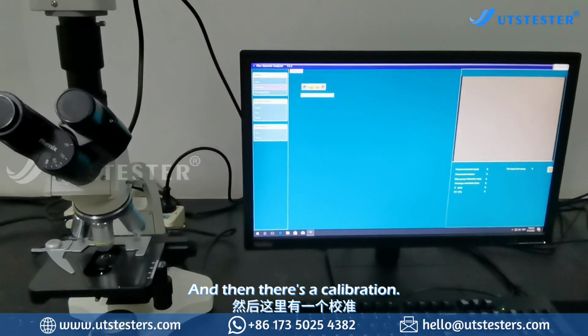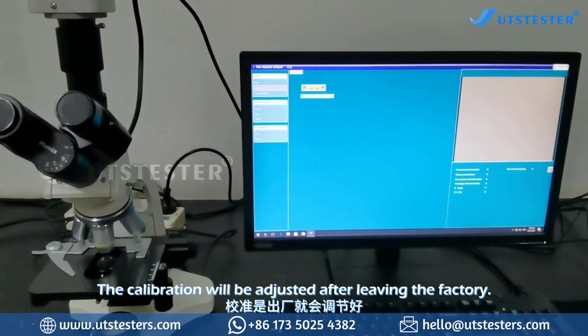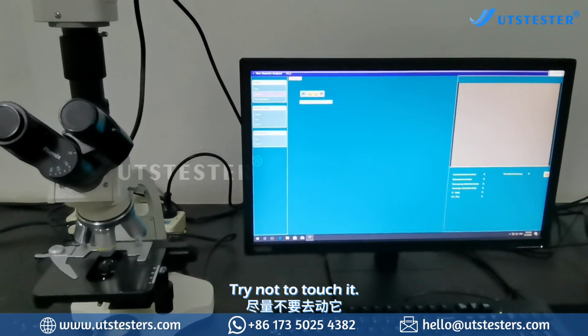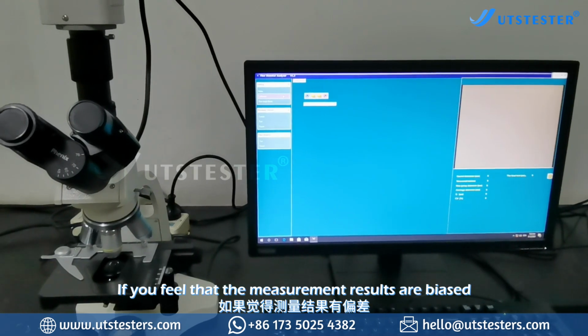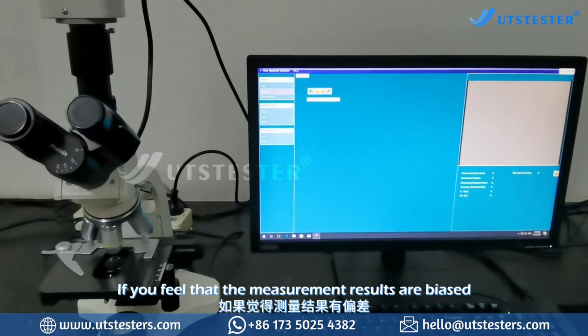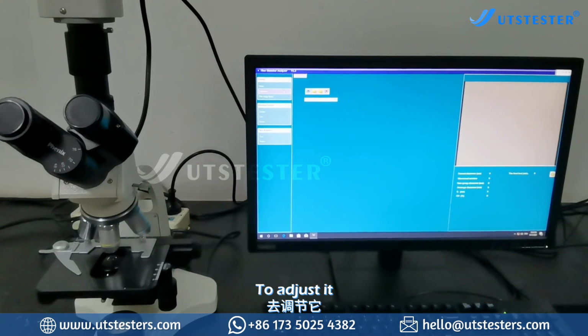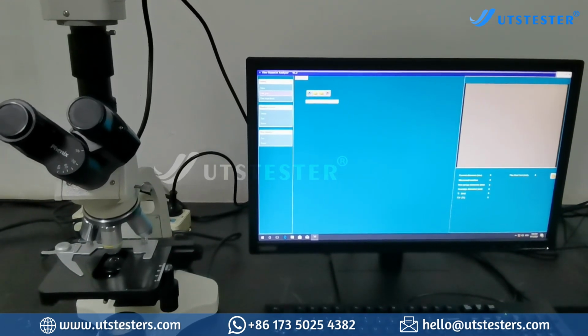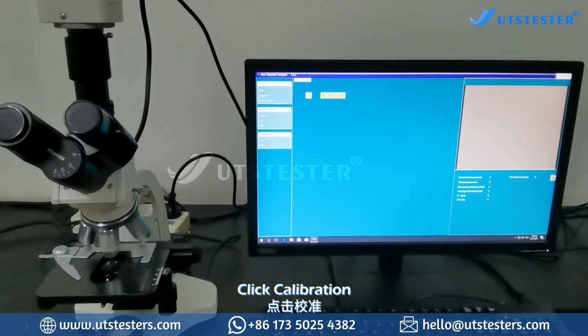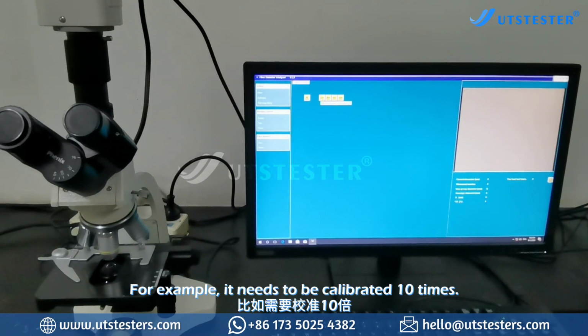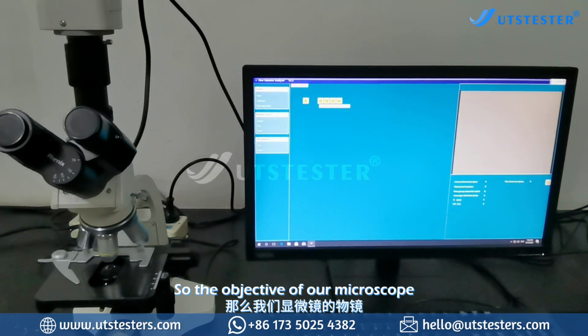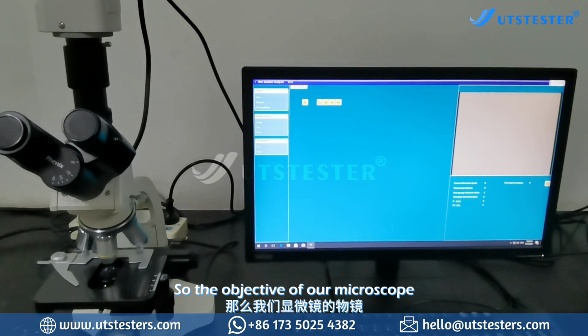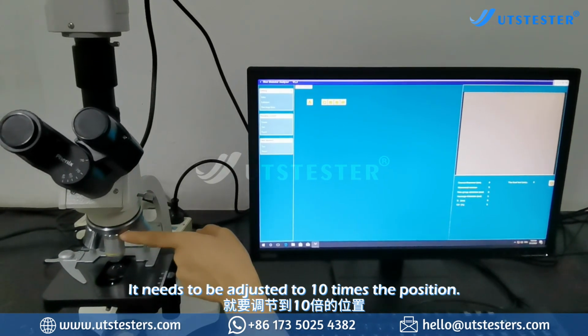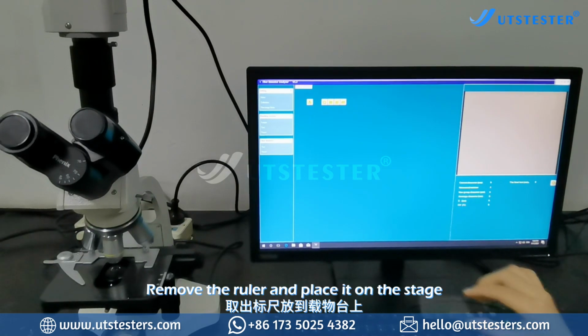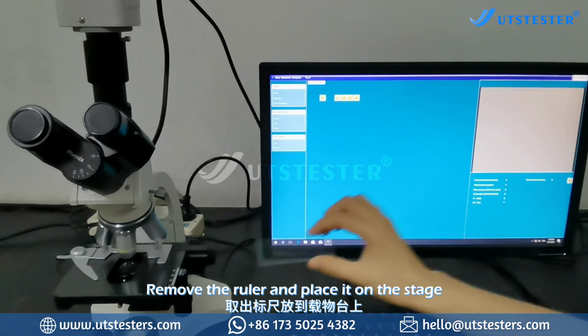And then there's calibration. The calibration has been adjusted after leaving the factory. Try not to touch it. If you feel that the measurement results are biased, to adjust it, click Calibration. For example, it needs to be calibrated at 10 times. So the objective of our microscope needs to be adjusted to the 10 times position. Remove the ruler and place it on the stage.